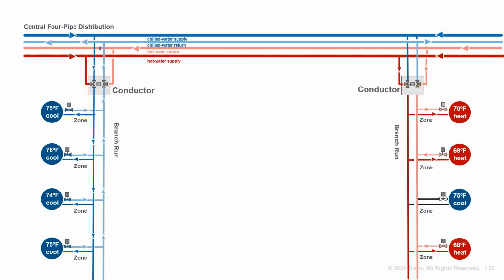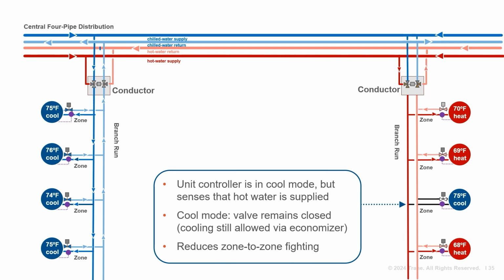The DAD just delivers heating or cooling fluid based on the current requirements of the thermal area, and may only switch over periodically throughout the year. Zones can be in heat mode when the area is in cool, or zones can be in cool mode when the area is in heat. Each zone has a temperature sensor to determine if hot or cold water is being currently supplied to the zone, so the zone level controller does not need to communicate with the BAS or the DAD to control. If a zone calls for cooling, but only hot water is currently being provided by the DAD, as in this example, the fan coil controller will not open the valve. This prevents zones from fighting.